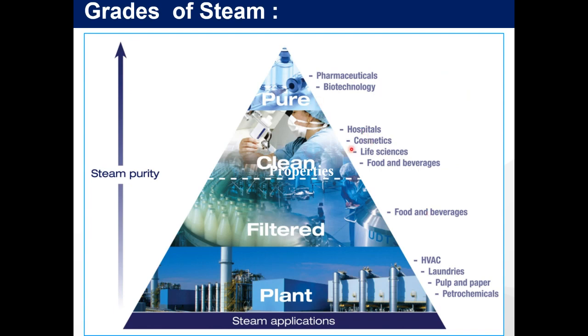Hospitals, they will use clean steam. So again, it's more filtration. We're talking now RO water in systems, clean steam system loops for hospitals, cosmetics, life sciences and food and beverage. And then you've got pharmaceutical and biotechnology, which will use ultra pure water, so demineralized water in their system. All stainless steel pipe works because the steam is most likely directly injected into product. Does anybody have any questions at this point?